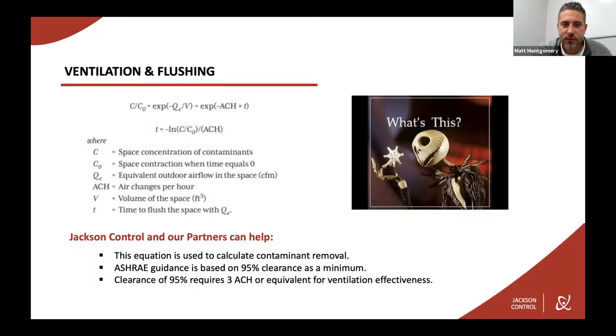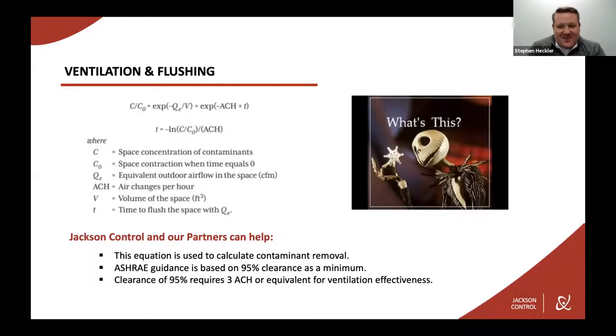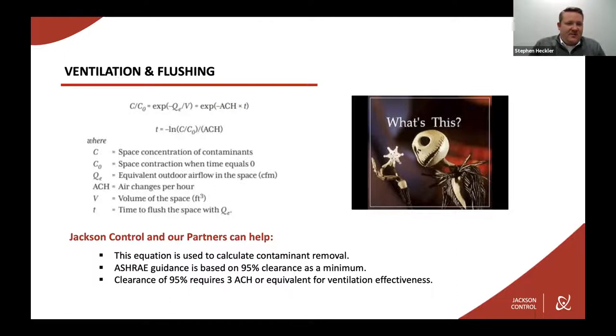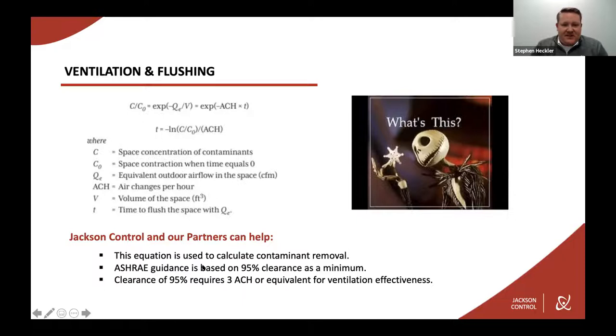I'm going to kick it over to Stephen Heckler to talk about ventilation and flushing. Ventilation and flushing starts with math. What we're looking for is ACH, which is air changes per hour. The equation shown and its variables are used to calculate contamination removal. You use that equation to look for a 95% clearance as a minimum, which is ASHRAE guidelines out of 62.1, and that typically requires three air changes per hour or equivalent. Whether you're using equipment or openings like doors and windows to get those air changes, you can run that calculation to figure out how often you need to move air.